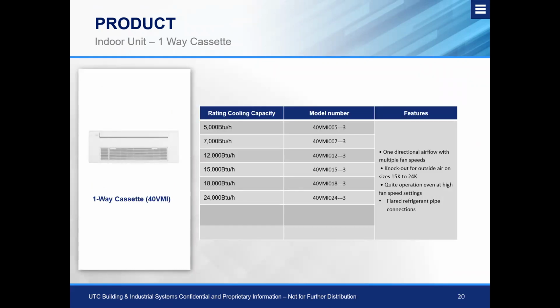With our one-way cassette, this is a new product that we brought in, I think it was 2020, might have been the beginning of 2020. This will range from 5 all the way to 24,000 BTU. That's a one-directional airflow with multiple fan speeds. I mentioned briefly that certain models in this range actually have an outside air knockout to introduce outside air. The 15,000, 18,000, and 24,000 BTU models have that knockout for outside air. Again, it must be pre-treated, but it certainly does offer some versatility on the 15,000 BTU model. And of course, just like every other indoor unit that we have on here, we have our flared refrigerant pipes for connecting us into the VRF.